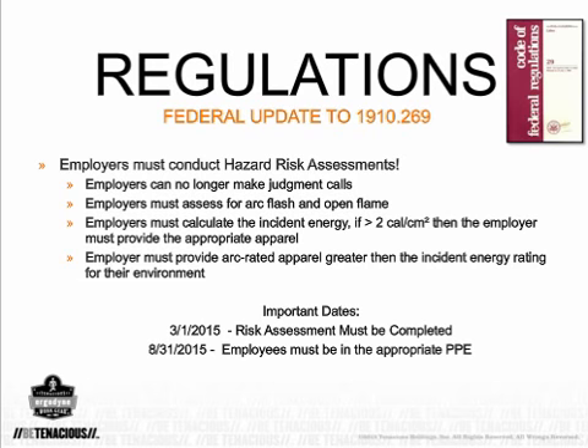If these hazards are present and/or if an employee could be exposed to 600 volts or higher, then the proper PPE must be provided. In addition, employers now must calculate the incident energy level. If greater than 2 cal per centimeter squared, the employer must provide the appropriate PPE. An employer must provide arc-rated apparel greater than the incident energy level of their environment.